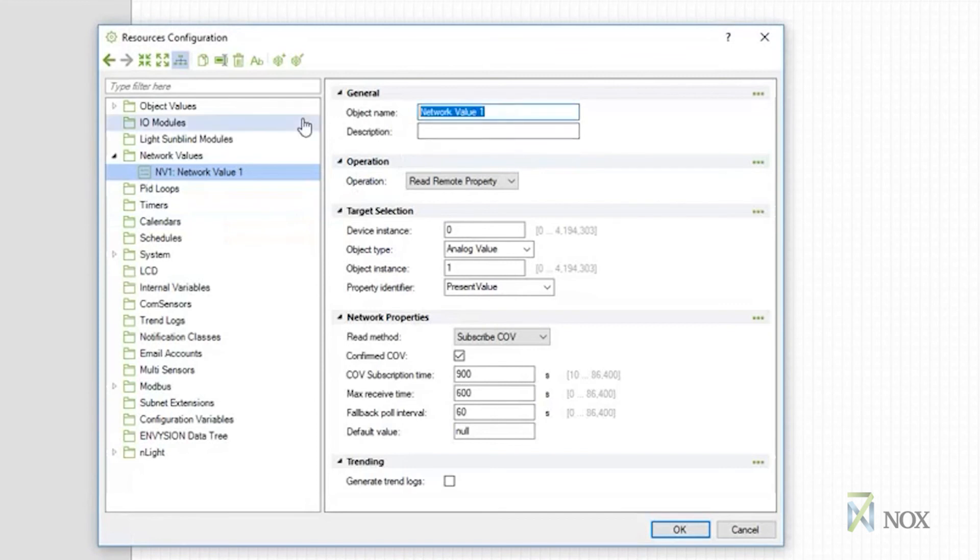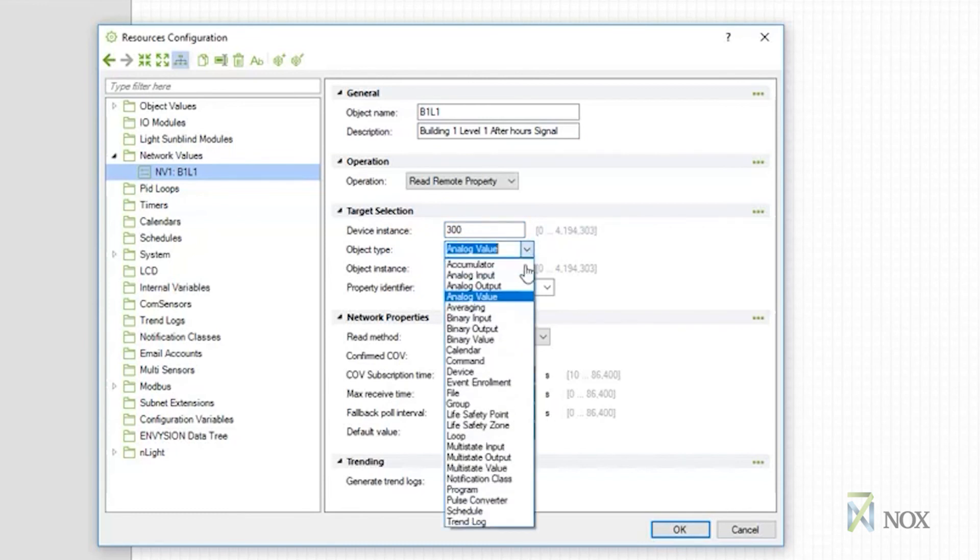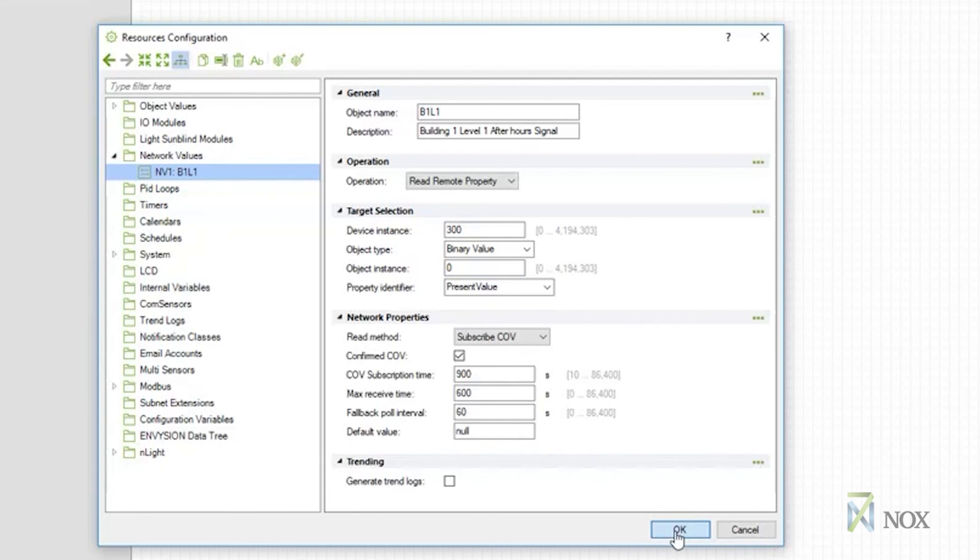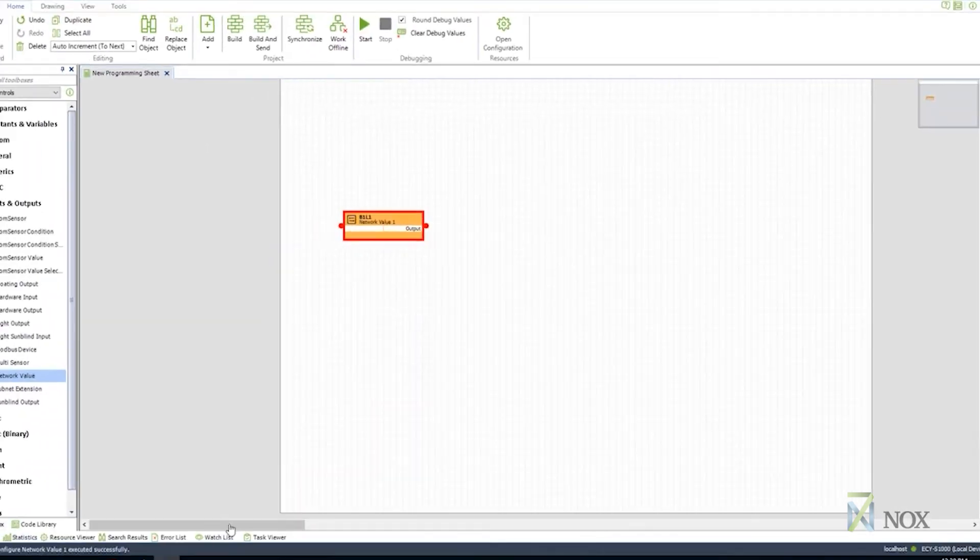Under the description field, we give it a more detailed description. We then configure the device instance to 300, object type to binary value, object instance to 0, property identifier to present value. Under network properties, we then configure the read method to subscribe COV, confirmed COV to checked. The other settings in this page we leave as default, such as the COV subscription, time, max receive time, fallback poll interval, and default value.